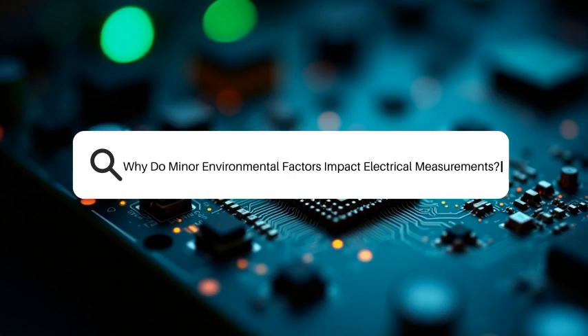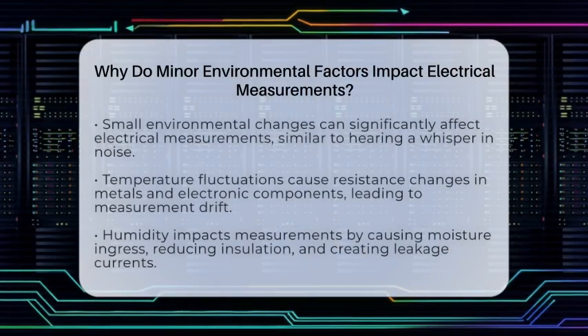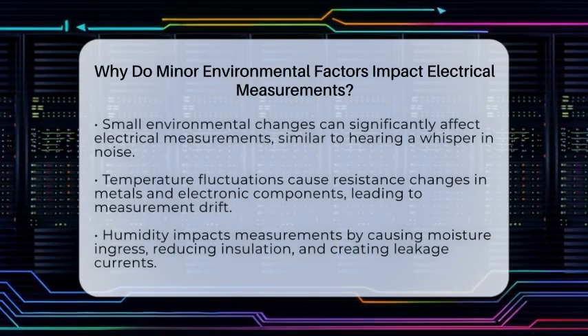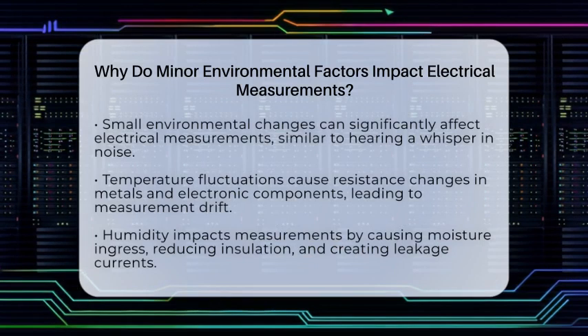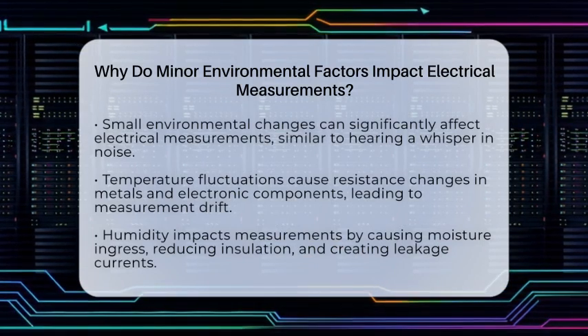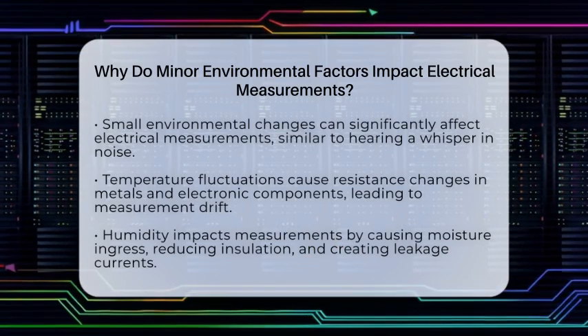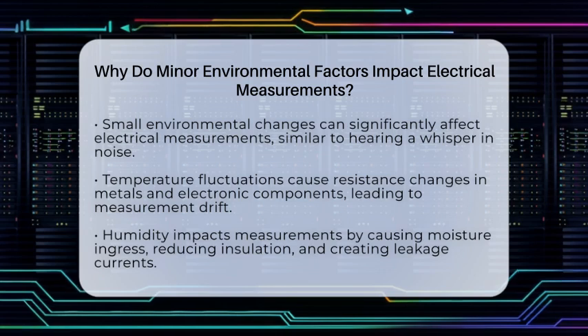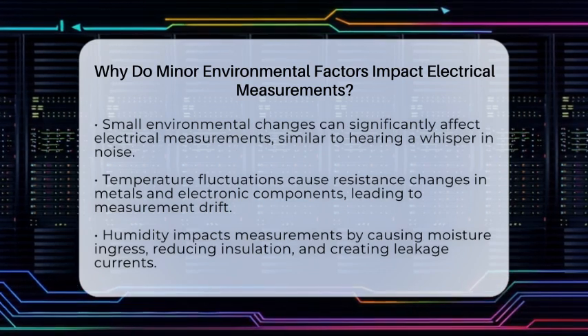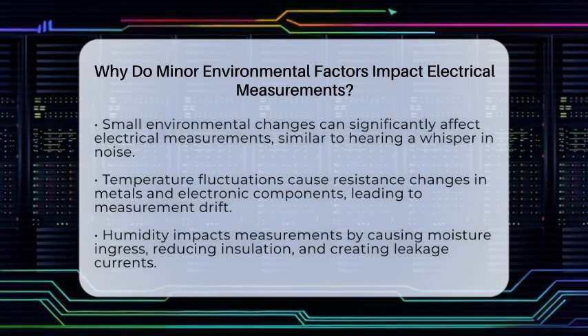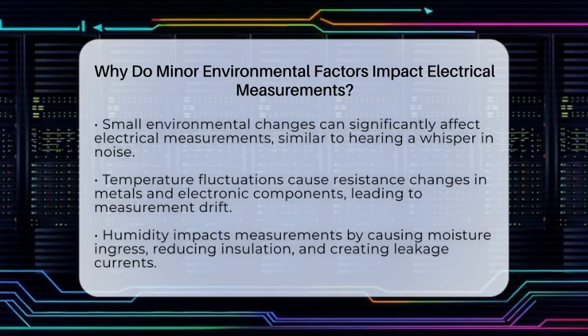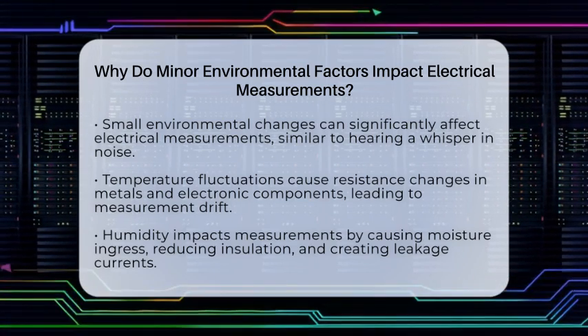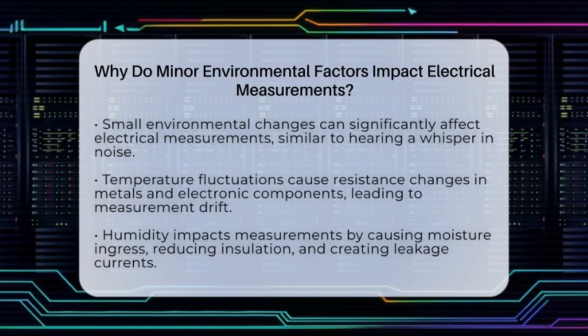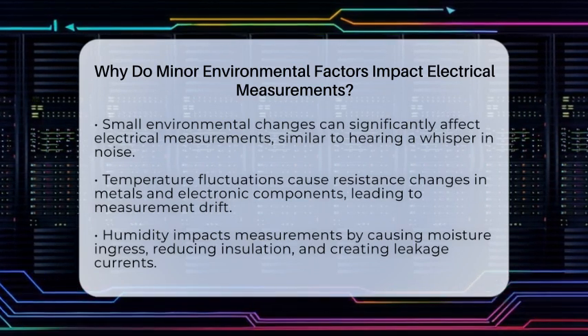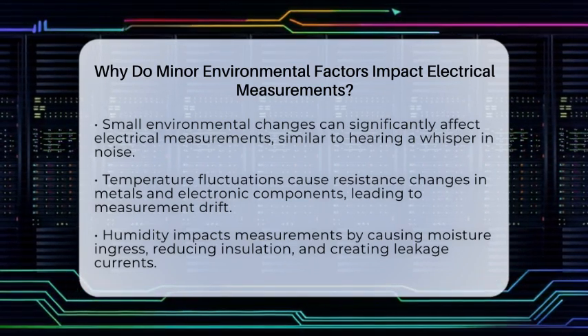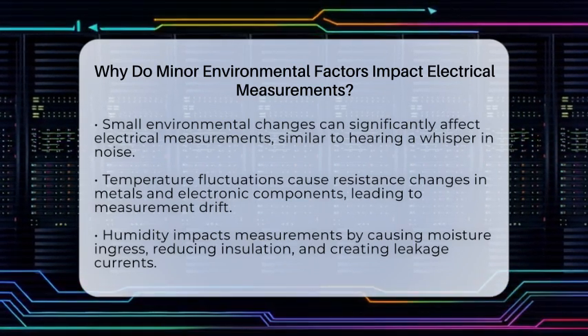Why do minor environmental factors impact electrical measurements? Imagine trying to measure something very tiny, like a whisper in a noisy room. Small environmental changes can make a big difference in electrical measurements. When we talk about calibrating test equipment or measuring electrical signals, stability is key. But even tiny shifts in temperature, humidity, pressure, or electromagnetic interference can throw off those measurements.